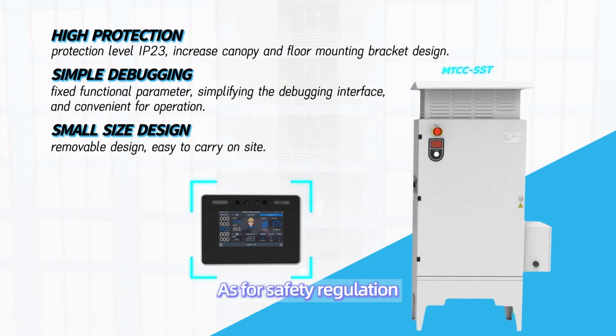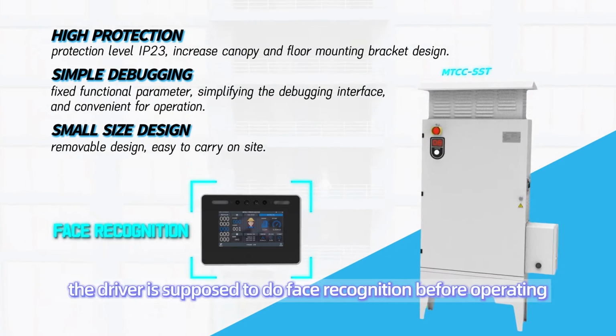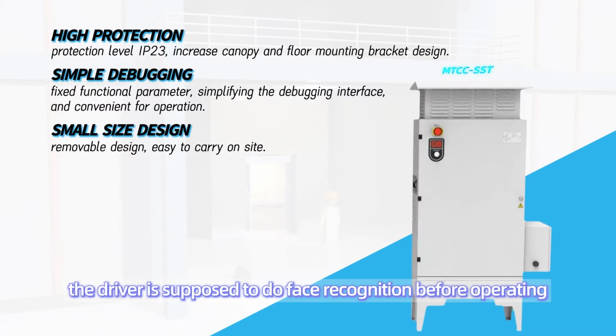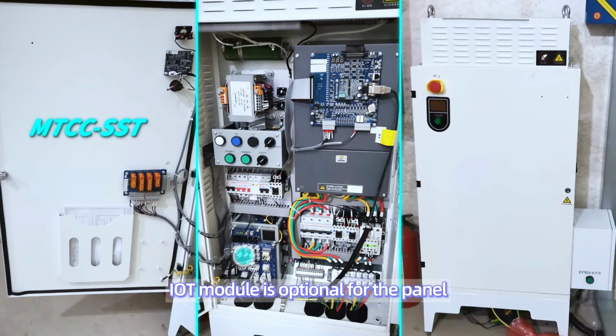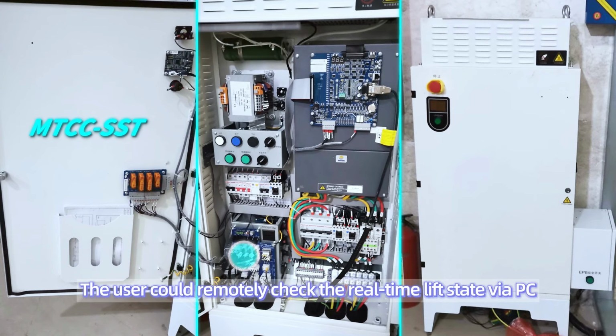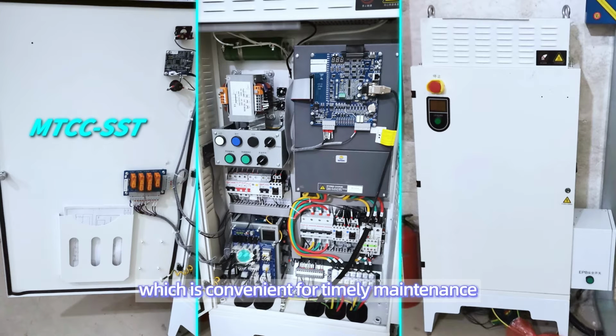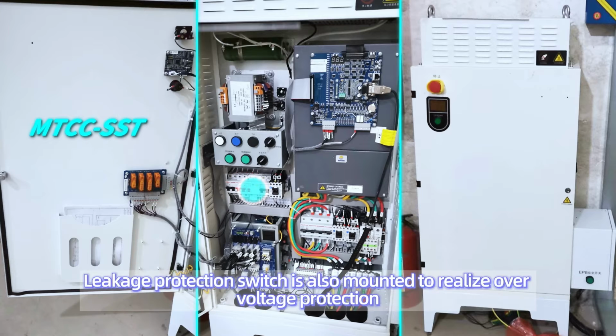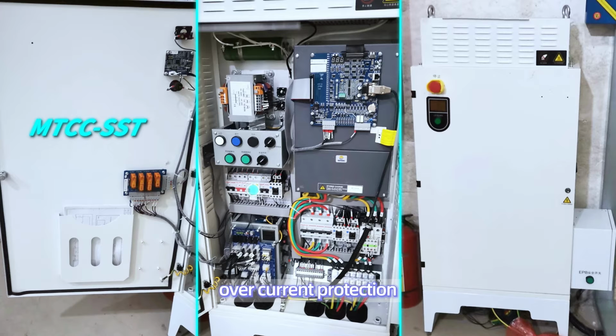As for safety regulation, the driver is supposed to do face recognition before operating. An IOT module is optional for the panel. The user can remotely check the real-time lift state via PC, which is convenient for timely maintenance. A leakage protection switch is also mounted to realize over-voltage protection, overcurrent protection, and short-circuit protection to ground.